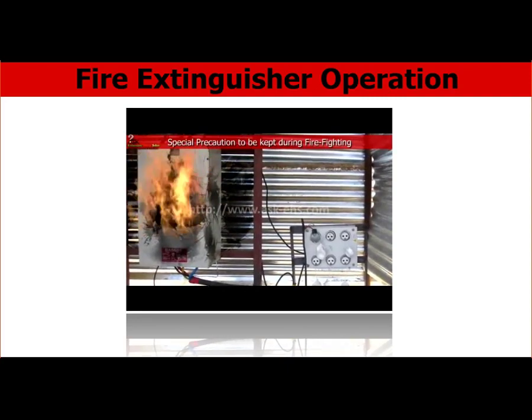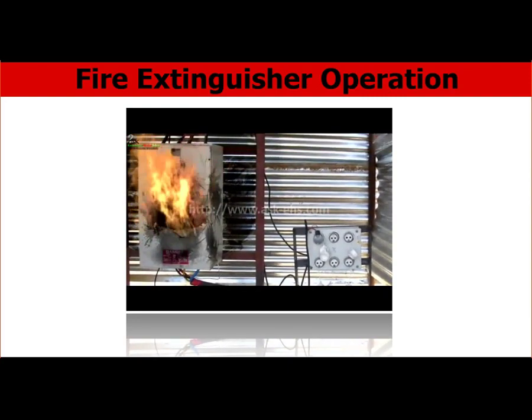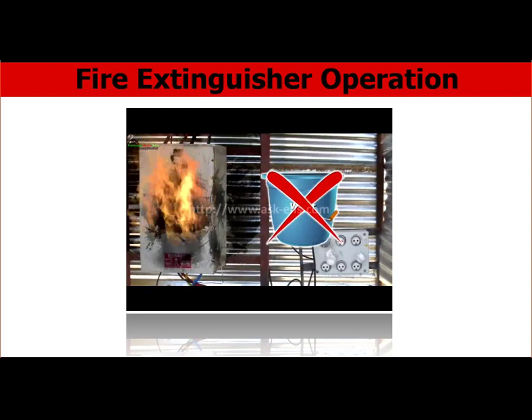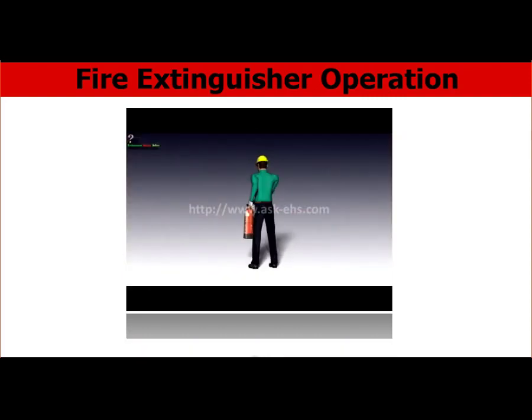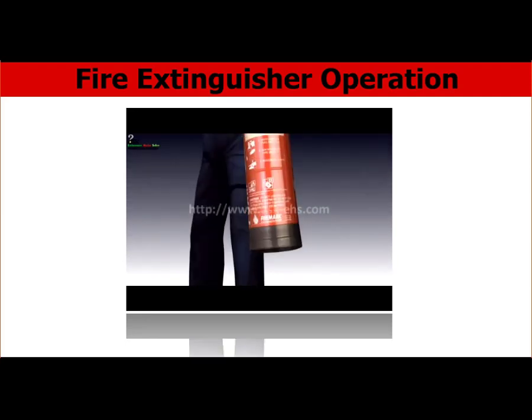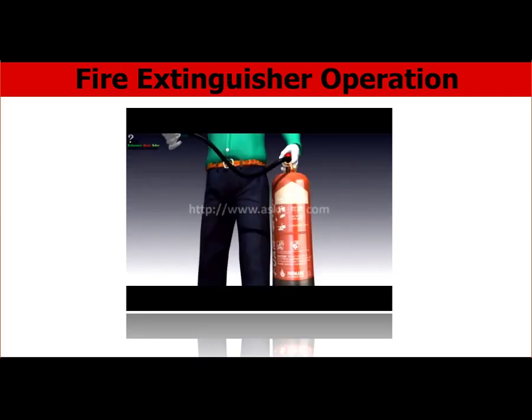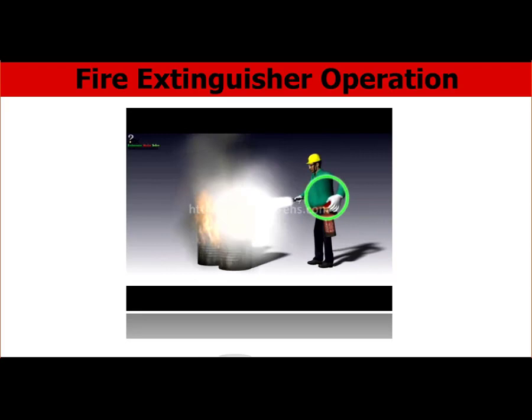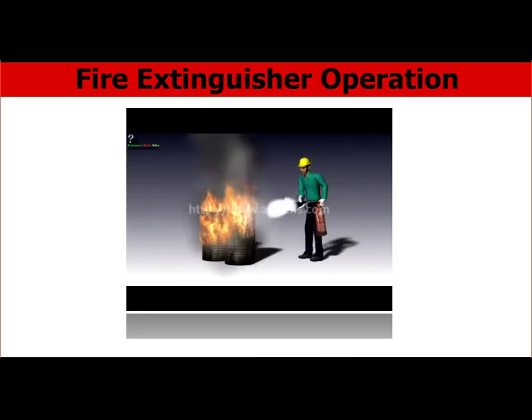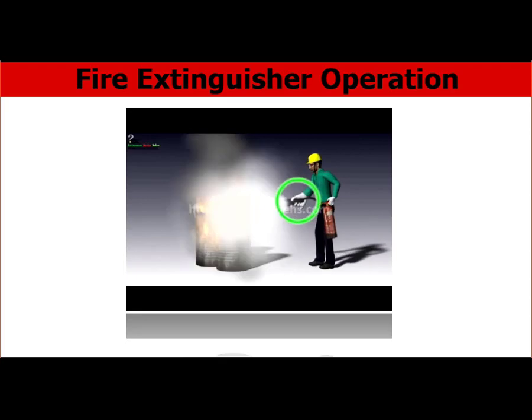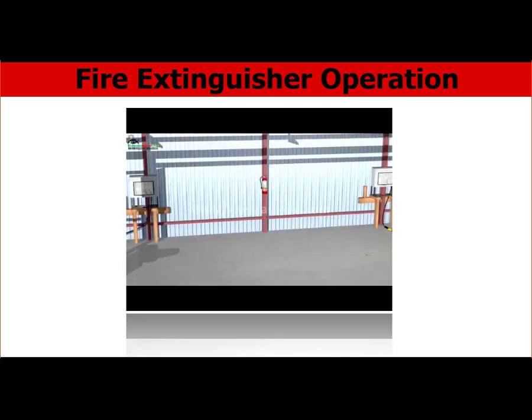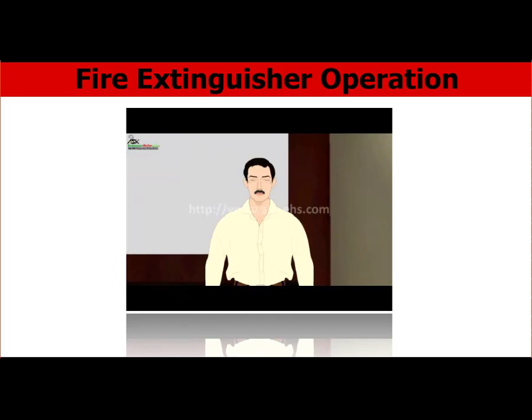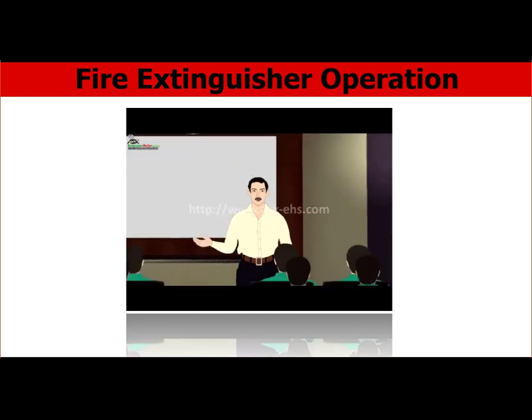Special precautions to keep in mind during firefighting: don't use water on electrical equipment — it may give an electrical shock. While using a carbon dioxide cylinder, the cylinder and hose become very cold and may cause a cold burn, so use it very carefully. Don't obstruct the way to a fire extinguisher. If you don't know how to fight a fire, seek help immediately.